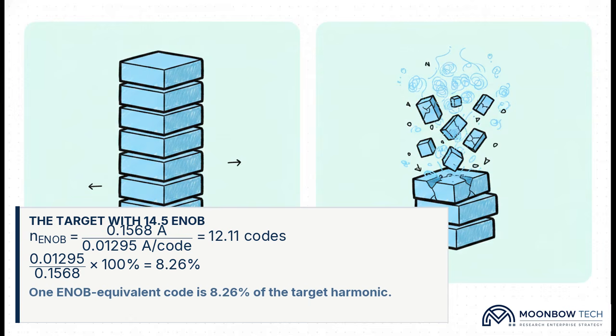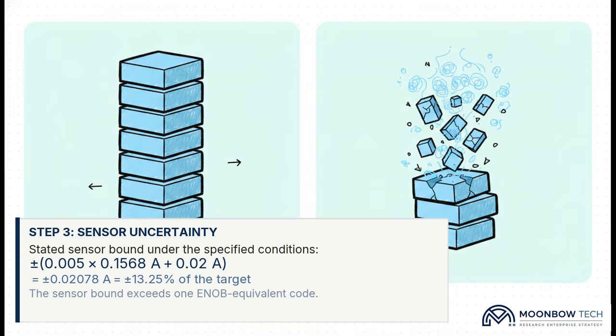Honestly, this brilliantly illustrates the danger of reading just the top line of a manufacturer's spec sheet. We plummeted from 34.25 ideal codes down to just 12.11 usable effective codes. The instrument's own internal limitations wiped out a massive chunk of our viewing window. And the craziest part? We haven't even factored in the physical sensor sitting outside the instrument yet.